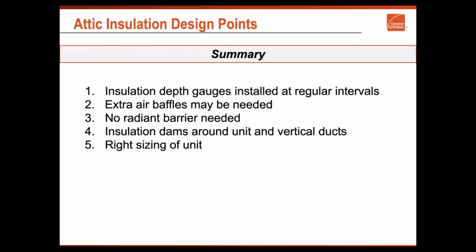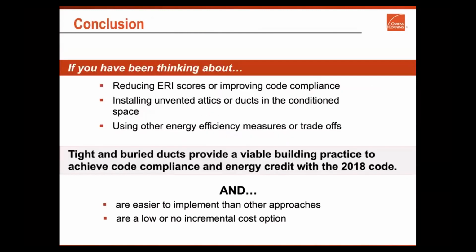And once again, the most vital, it's last, but it's not least, is right-sizing the unit. If you oversize the tonnage, you're going to cause short cycling, causing comfort issues, causing mold, causing a lot of issues in a home. And that's one thing that we have to avoid.